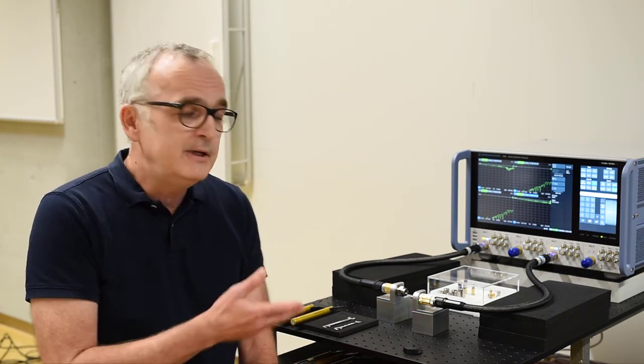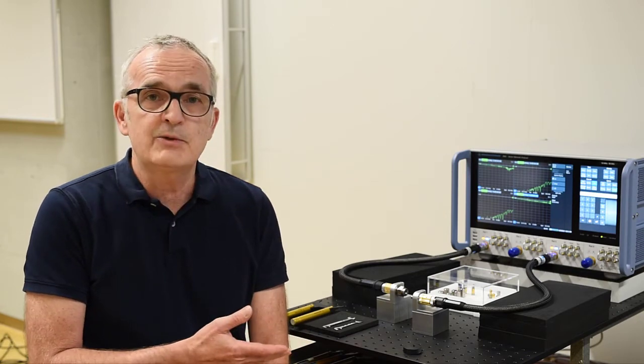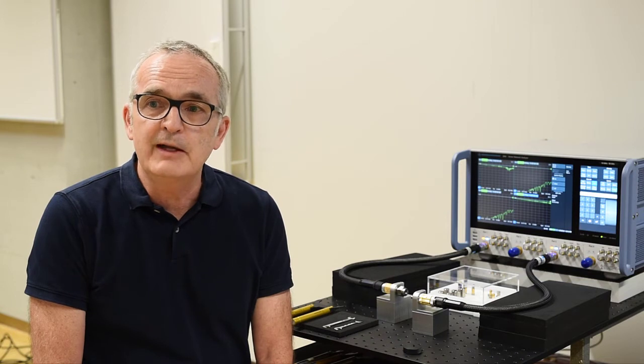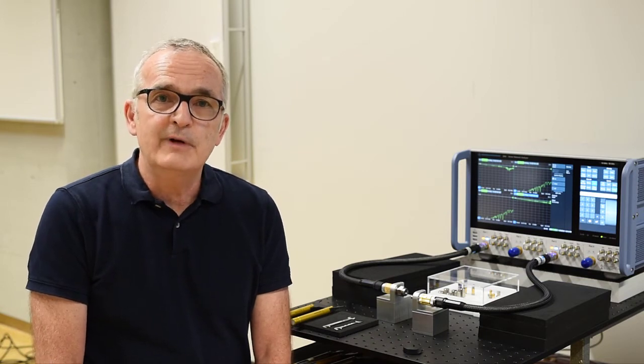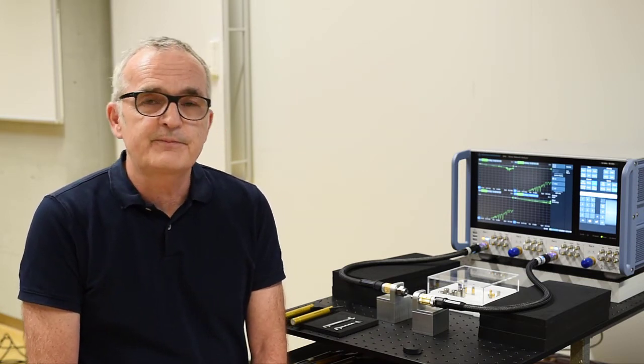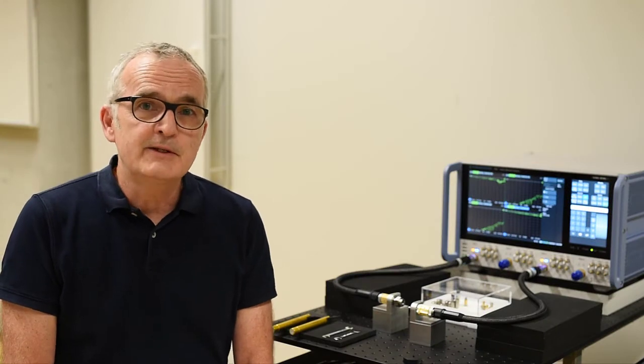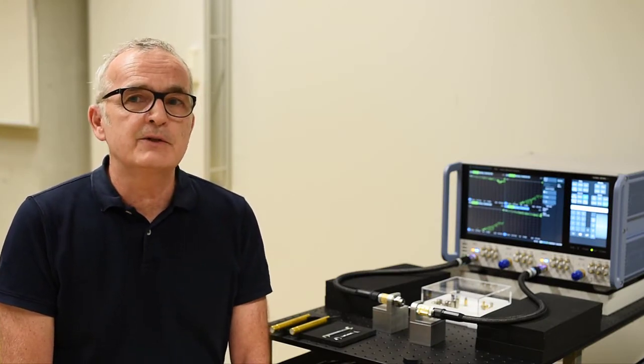In this example here, we would like to show you an SOLT calibration using 2.92 mm connector family and show you some verification measurements. The following steps describe the typical use of Vna tools.